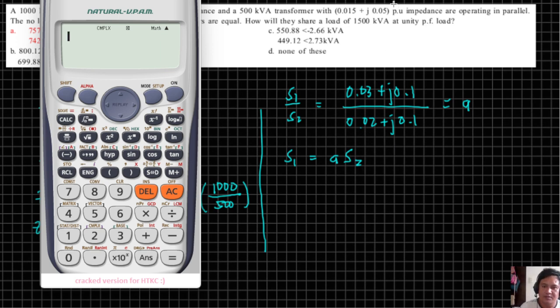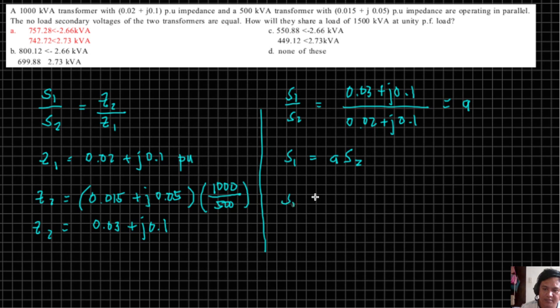The load is 1500 kVA at unity power factor. When operating in parallel, S1 plus S2 equals the total load, which is 1500 at angle 0 since it's unity power factor. That's our equation 1.